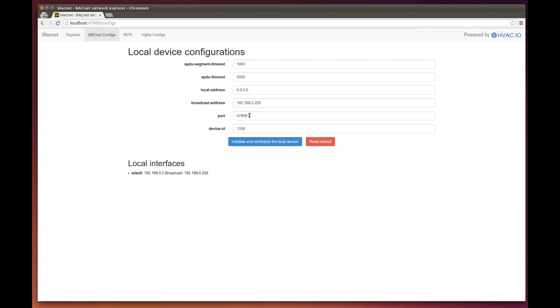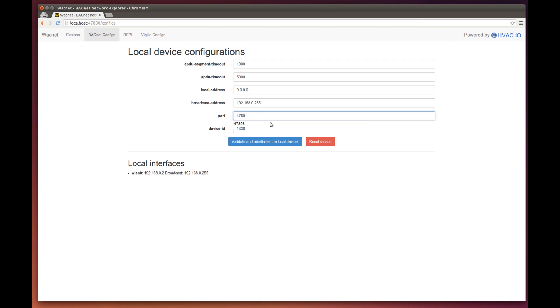There are some cases where you might require more than a single BACnet network. Usually, in those cases, the next port chosen is 47809, 47810, and so on.